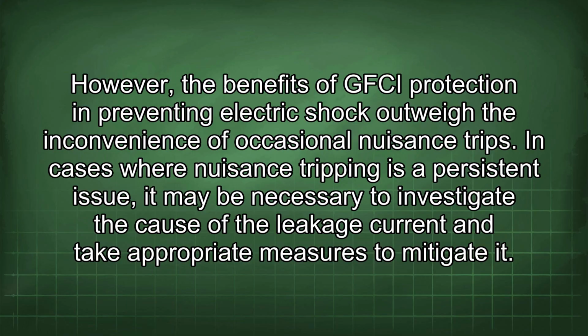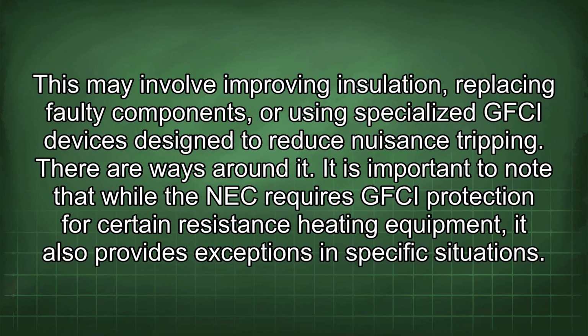In cases where nuisance tripping is a persistent issue, it may be necessary to investigate the cause of the leakage current and take appropriate measures to mitigate it. This may involve improving insulation, replacing faulty components, or using specialized GFCI devices designed to reduce nuisance tripping. There are ways around it.